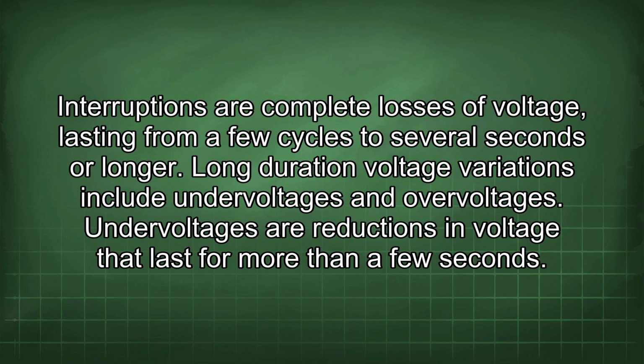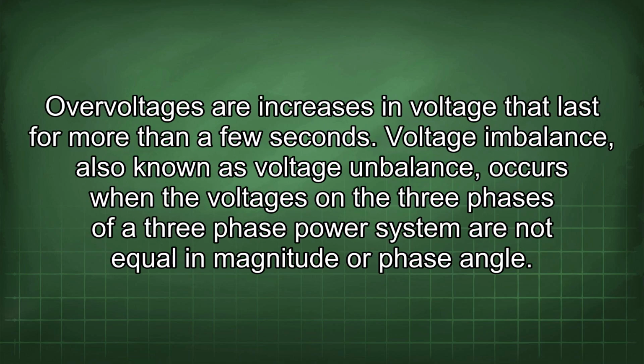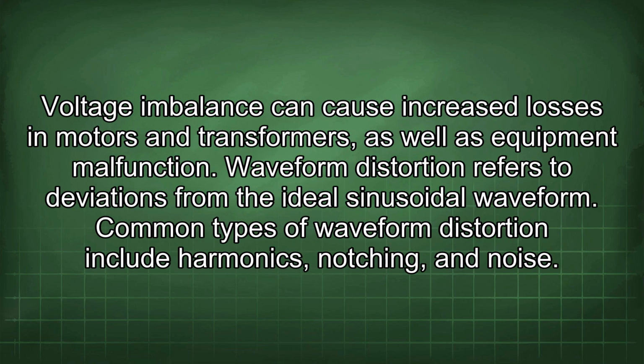Undervoltages are reductions in voltage that last for more than a few seconds. Overvoltages are increases in voltage that last for more than a few seconds. Voltage imbalance occurs when the voltages in the three phases of a three-phase power system are not equal in magnitude or phase angle. Voltage imbalance can cause increased losses in motors and transformers, as well as equipment malfunction.